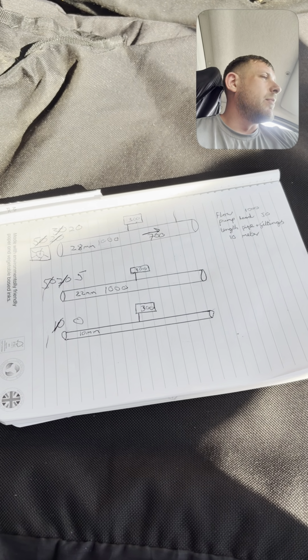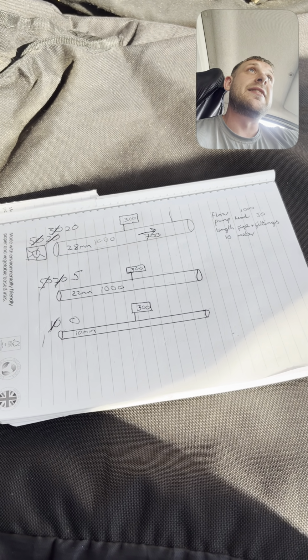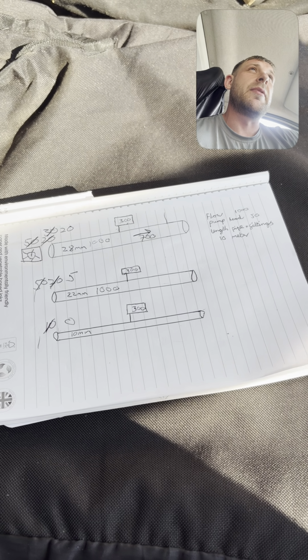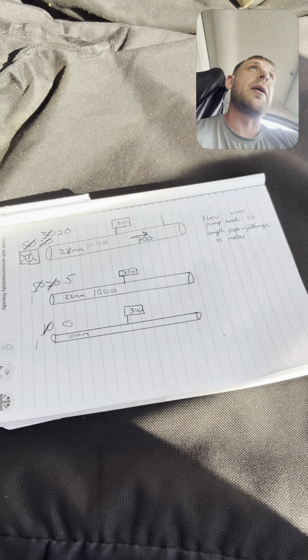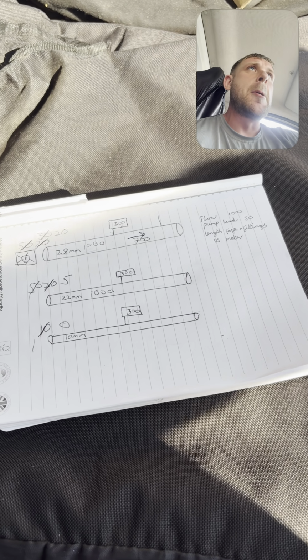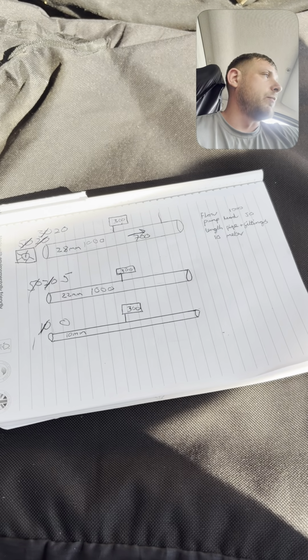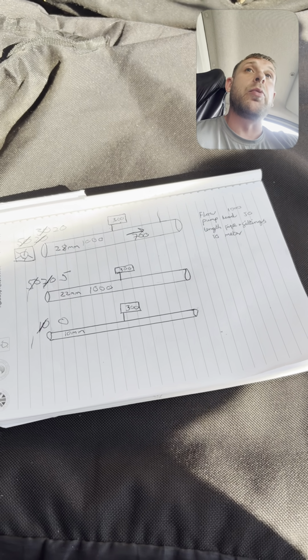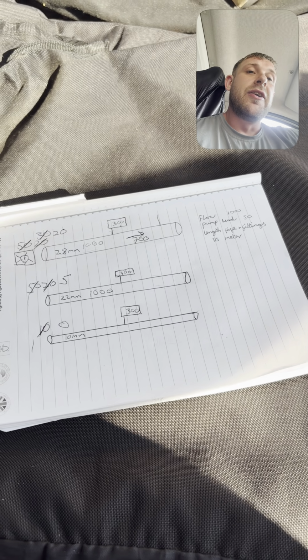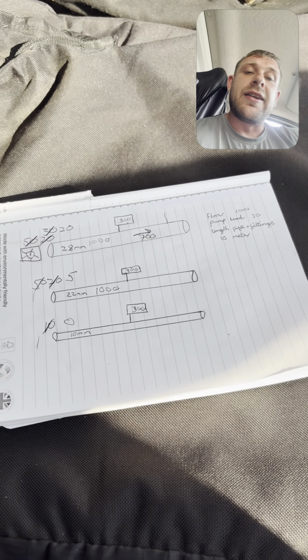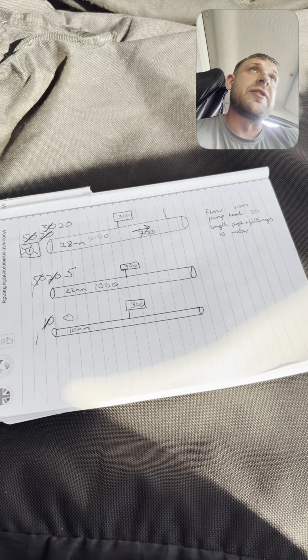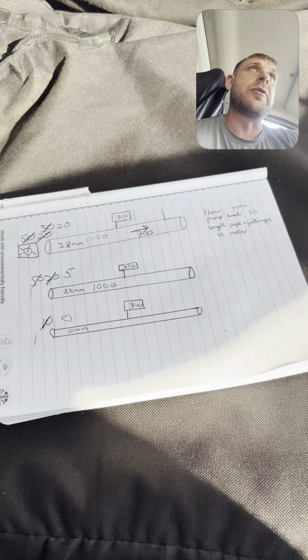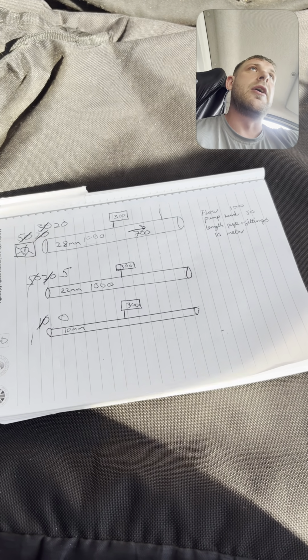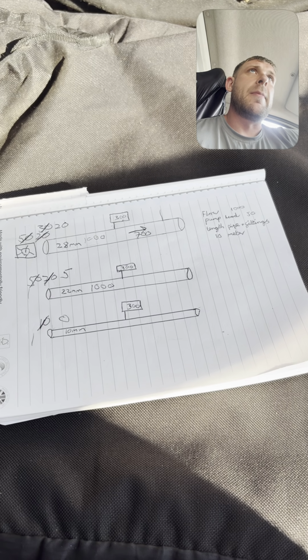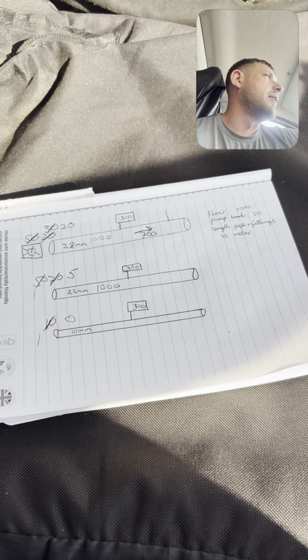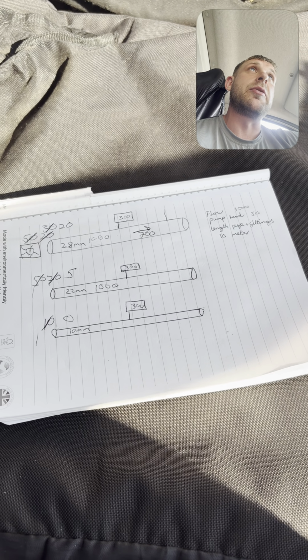I remember one of the very first system designs I completed for a heat pump. They had electric storage heaters, so I was doing the full pipe layout and working out the pipe sizes needed. When I was working it out, it actually came back that 10mm pipe would have been the perfect size to use in that central heating system I was designing. It gave us the perfect velocities that we needed. The pressure losses were perfect. We had the pump head available, and I was like, what's going on here? 10mm pipe.